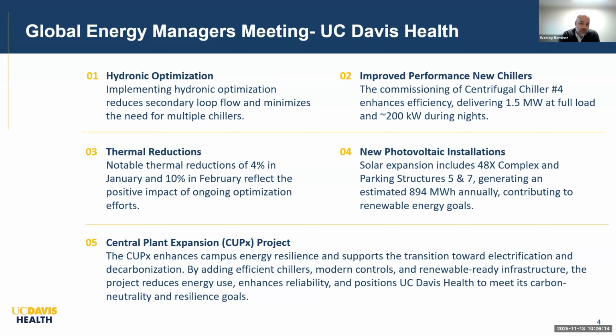Item number 2: improved performance from new chillers. We recently opened a new surgical center, the 48th and X complex, around July this year, which installed a new centrifugal chiller, number 4. It's now our primary chiller and operates significantly better than our other existing chillers. At full load it's only about 1.5 megawatts, and at nighttime operation around 200 kW. Our best-operating older chiller is really around 400 kW for nighttime operation, so a significant energy savings there.